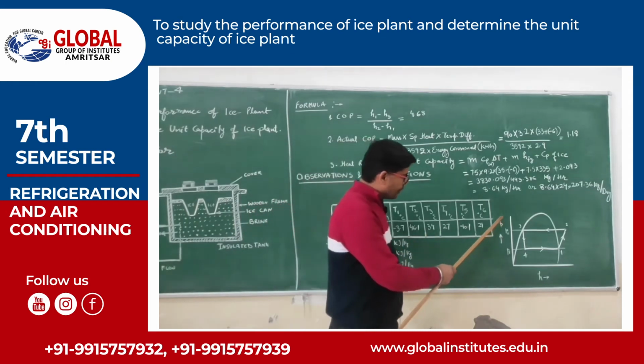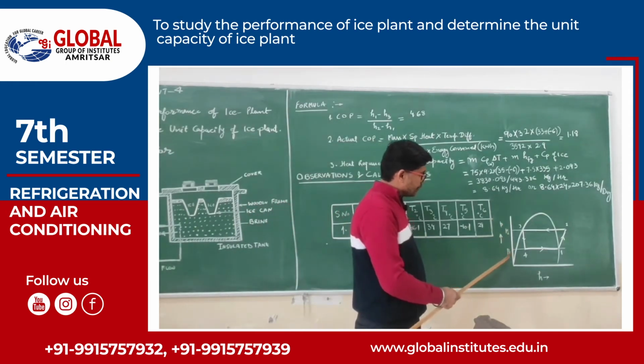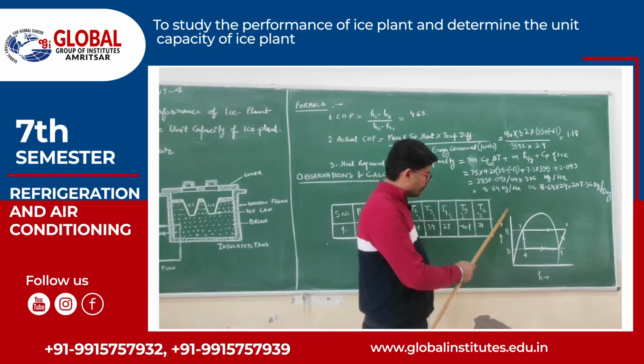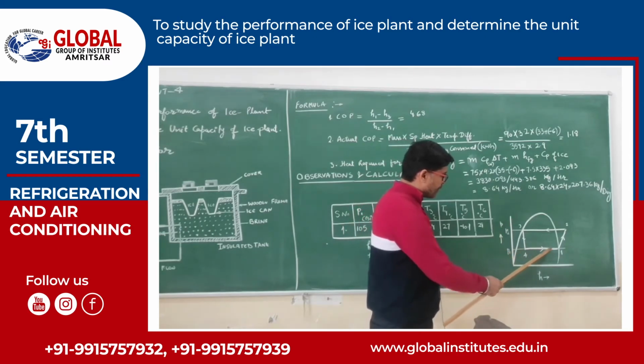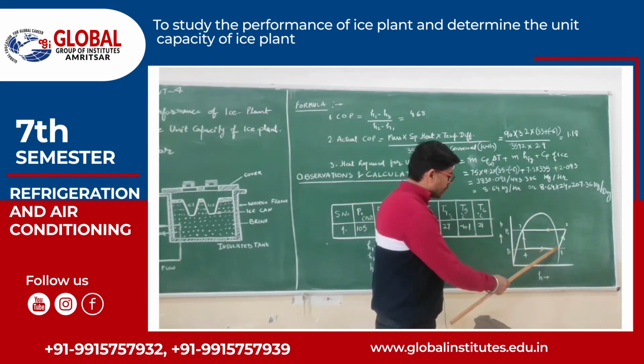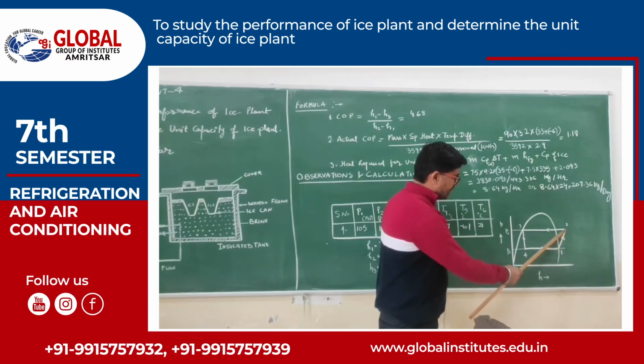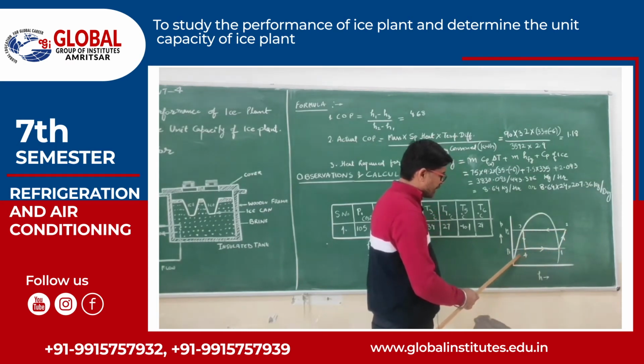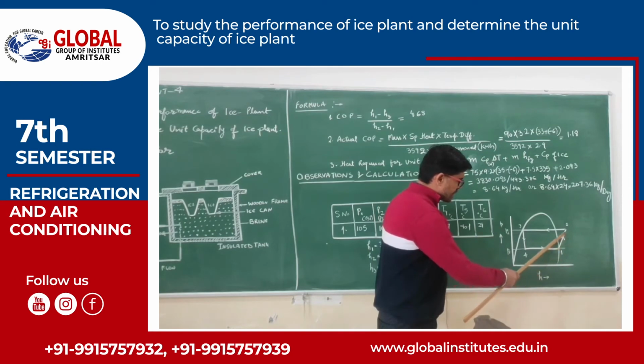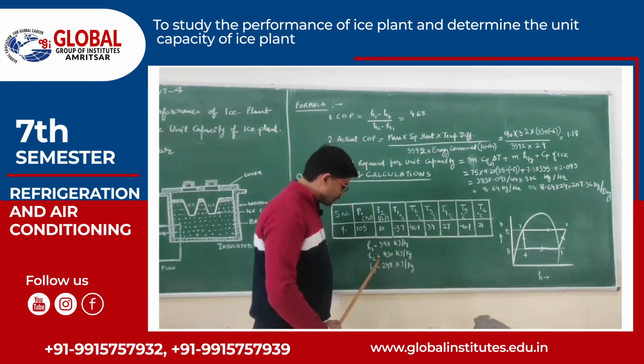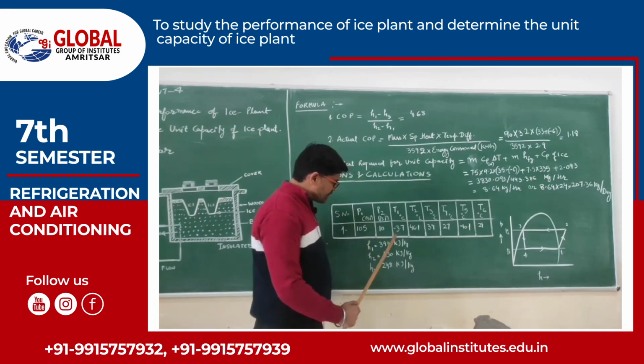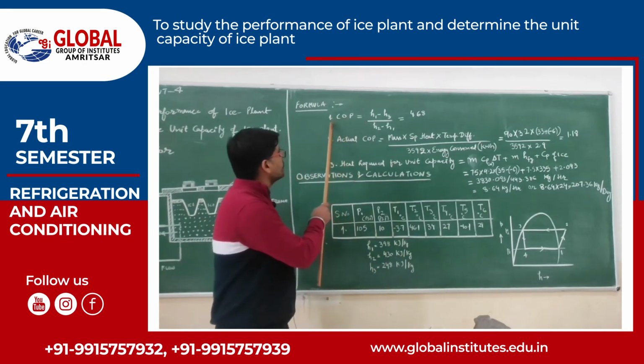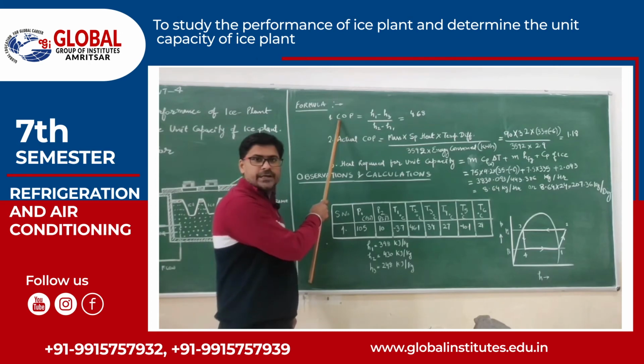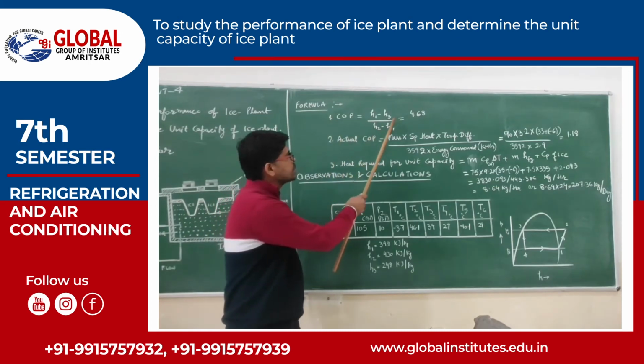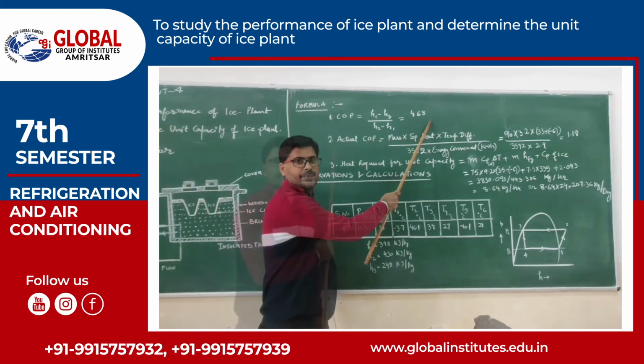After that, open the R134a p-h chart of the refrigerant and mark P1 and P2 and locate the T1, T2, T3, T4 temperatures, and corresponding to these temperatures find out H1, H2 and H3. These values are put into the first equation and we calculate the coefficient of performance, that is equal to 4.68.